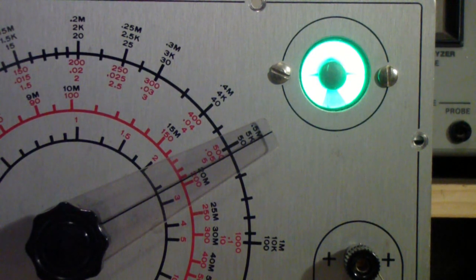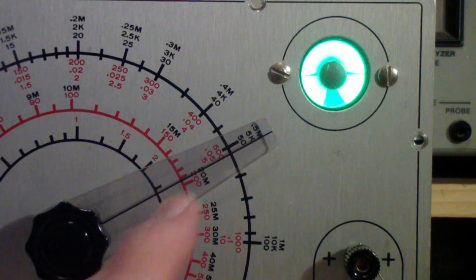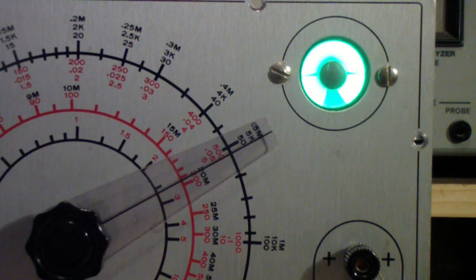By the way, I am comparing these capacitors to the Sencore at the same time, the LC102, just to see how accurate this RC bridge is. It's close, but not real exact. This particular capacitor is very close to 470 on the Sencore. Now, the Sencore hasn't been calibrated in a while, so I can't guarantee it's any more accurate than this EICO, but I depend on the Sencore a little more because I've used it a lot over the years, and it has always seemed to be pretty accurate. So I'm guessing this bridge is reading a little bit high on this highest capacitance range.